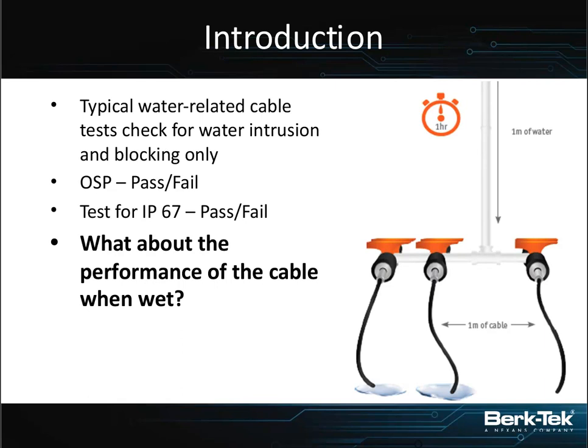The labs have been doing a lot of tests related to traditional water blocking outdoor cables and industrial-style cables over time. The tests we were doing were qualification-style tests - pass-fail: does water get through, does water reach electronics, or could this cable, if damaged, cause a critical failure because it was in a wet location?